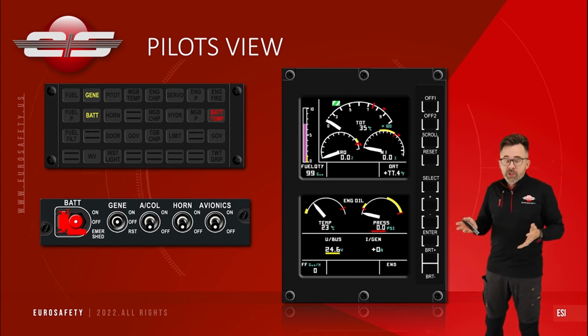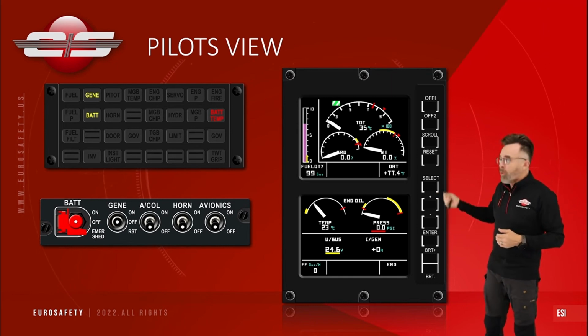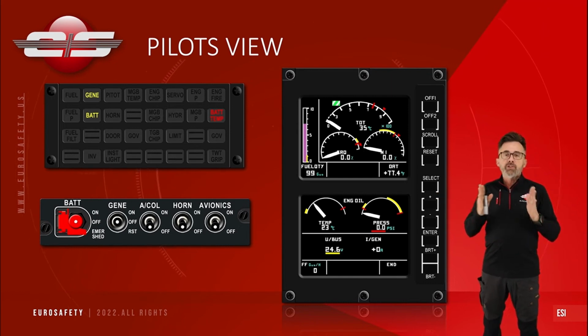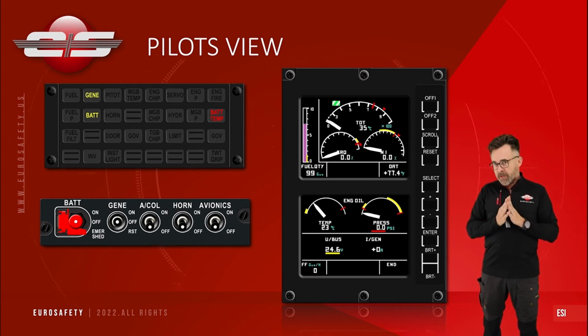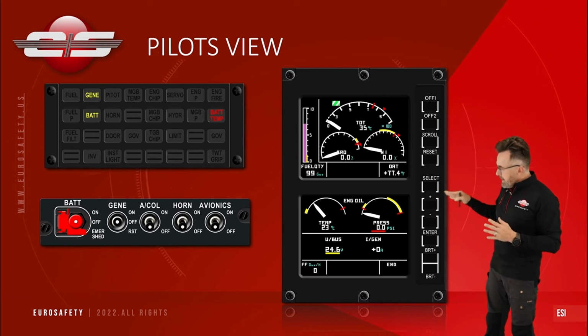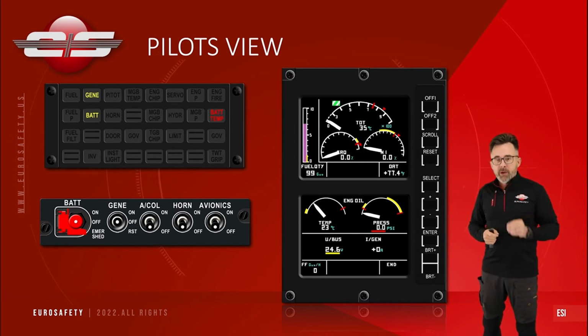And if you're in the off position, it's obviously not online. So when you go to on, it simply tries to close that relay as long as that generator, again, is producing more volts than is on the main distribution bus, it'll allow that relay to close.